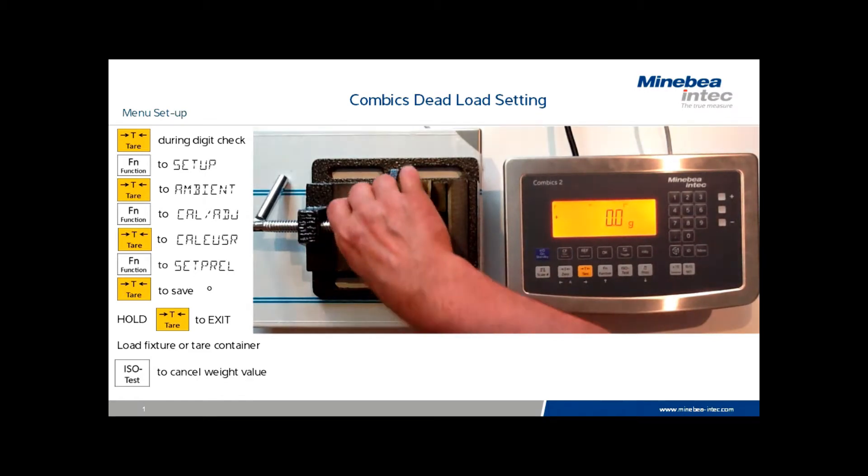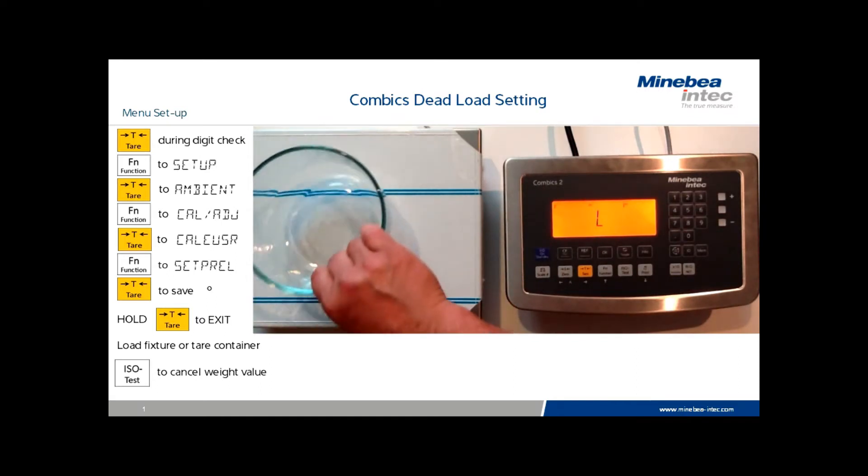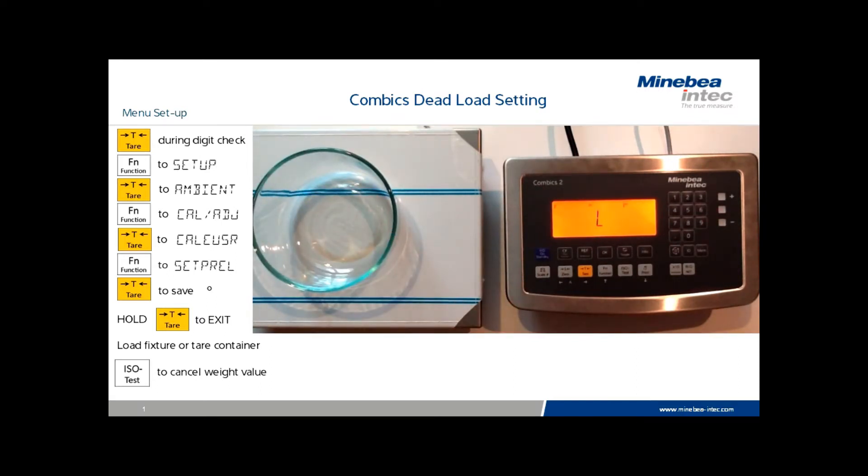It is possible to change to different fixtures simply by adding the new tare vessel or fixture in place. Press the ISO test key again, and the new fixture will be set as the preload.